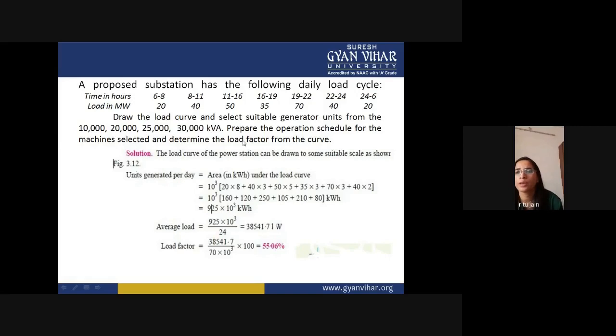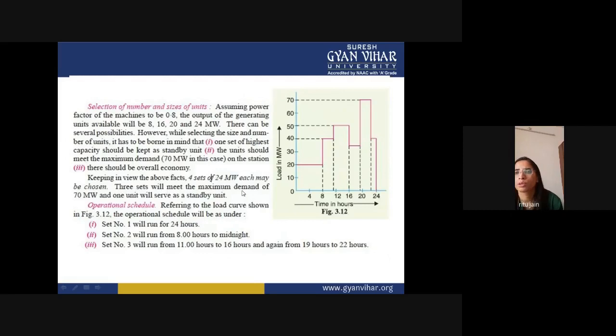Now it is saying that you have to select the suitable generator unit through the machine. So we can assume how we can select the number and size of units. We are assuming that the power factor of a machine is 0.8. Now the amount of power generating from units available will be 8, 16, 20, and 24 megawatt. This is your 4 units. Okay. So there can be several possibilities while selecting the size and number of units.